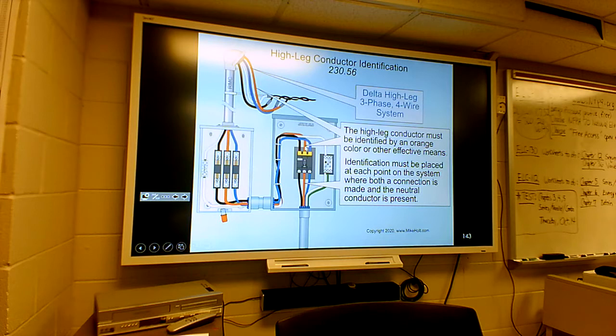When you use all three of those, the funny thing is, if you read, say, from black to orange, or black to blue, or orange to blue, in relation to each other, you'll get a standard reading like you're supposed to, a 208 or 240. It's okay. The problem is from the orange leg to neutral, it will read high because of the design of the transformer. Without getting into that, we'll get into that stuff that'll show you the reason. How many of you have had commercial wiring?